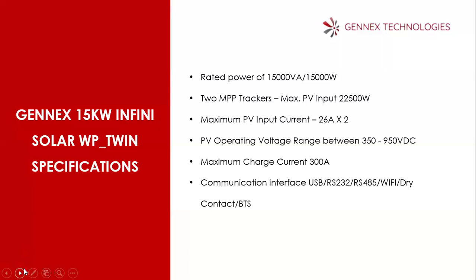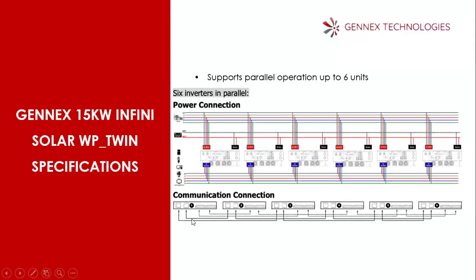Then again, it supports parallel operation of up to 6 units, which means 15 kilowatts times 6 units. You can achieve 90 kilowatts output when you connect the six inverters in parallel. And this is on 3-phase, which makes it robust, and you can also have your smart load on the dual output.